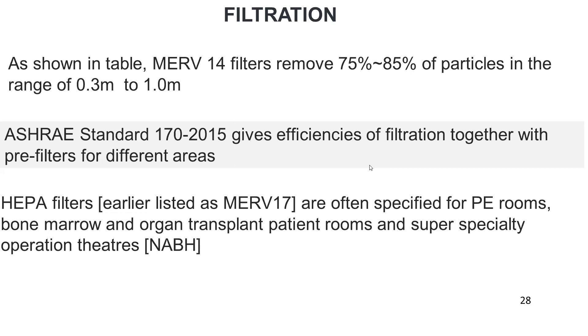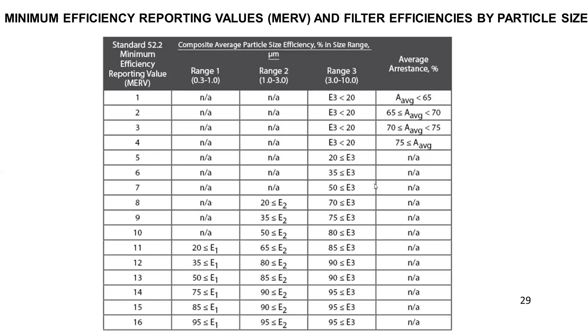HEPA filters, earlier listed as MERV 17, are often specified for PE rooms, bone marrow and organ transplant patient rooms, and super specialty operation theaters. And this is the MERV rating chart, and this is the HEPA filter rating chart. So this is just as a matter of detail, I'm showing it.